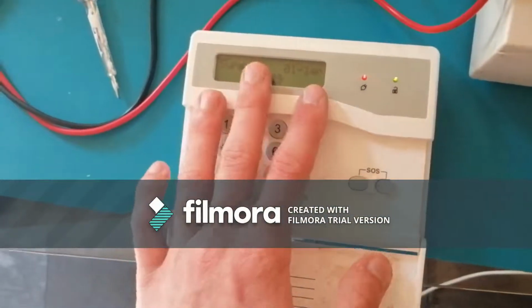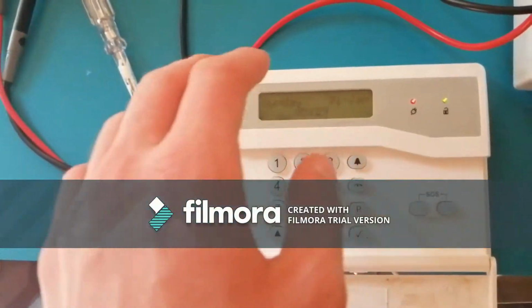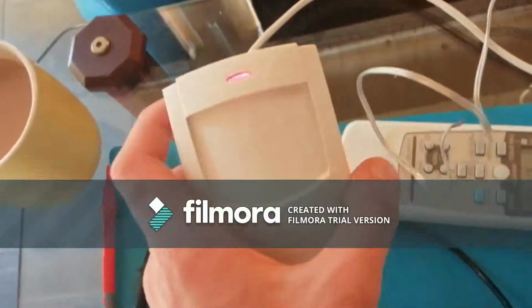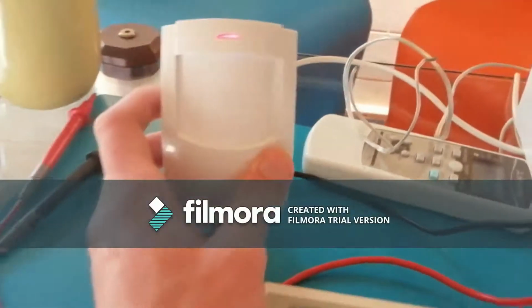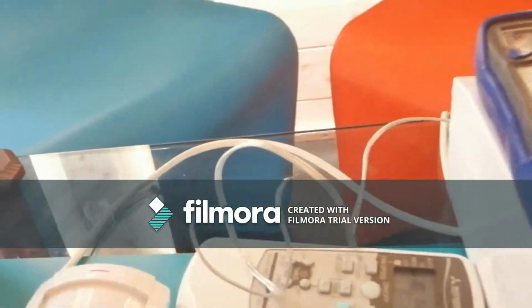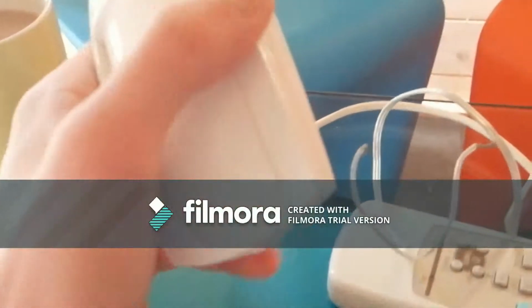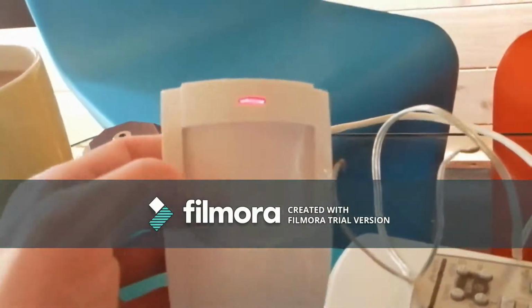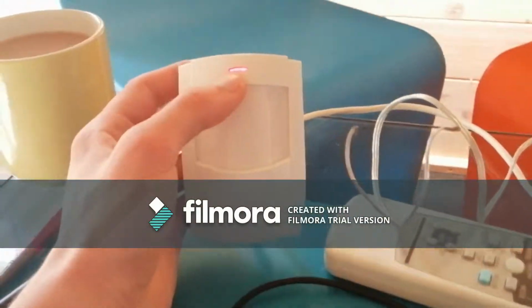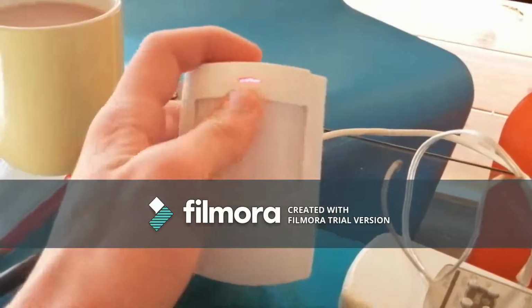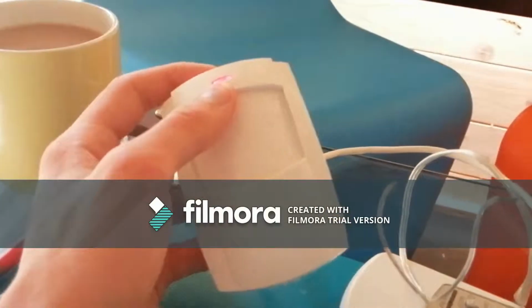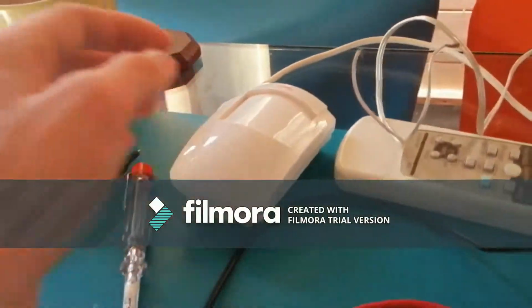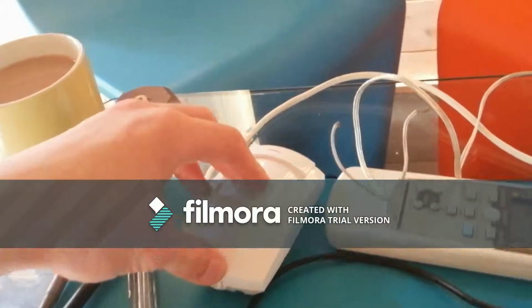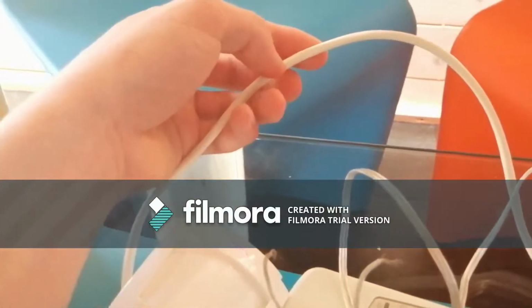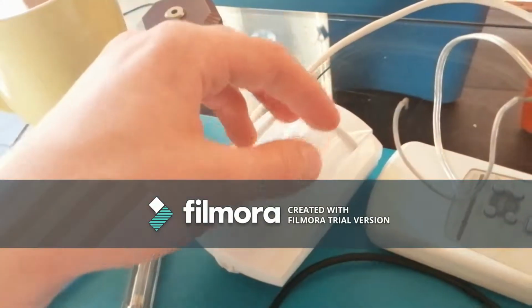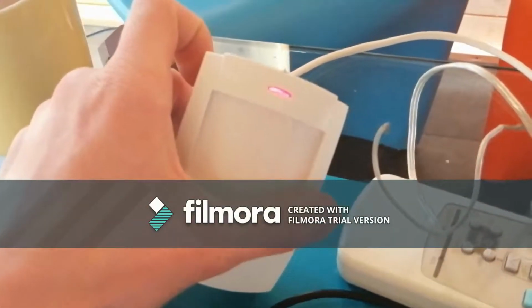So once you've identified the zone, then you go to the detector in question. If it is a detector, I'll talk about a door contact in a minute, but if it's a detector, then what you want to look out for is the LED. Okay, so if you walk into that room and the LED on that detector isn't illuminating, then you can tell just by that it is either a cable fault to the detector, so it isn't receiving any power, or it is the detector that's faulty.